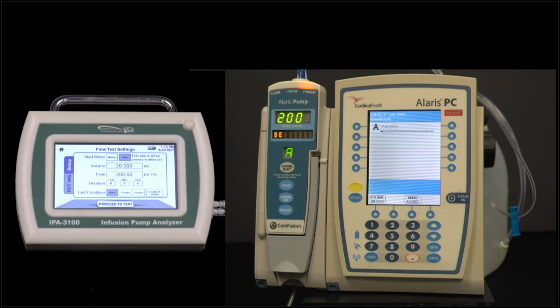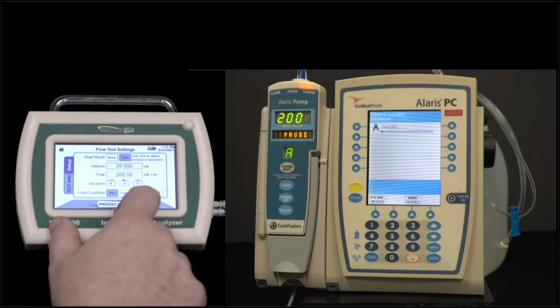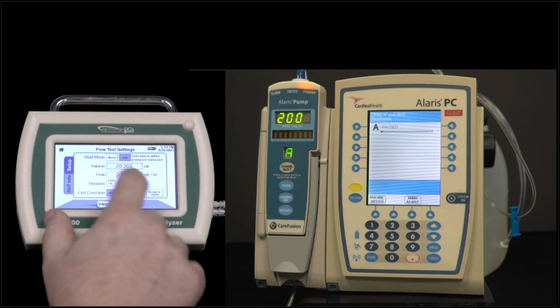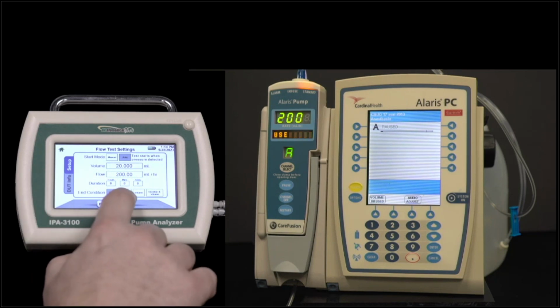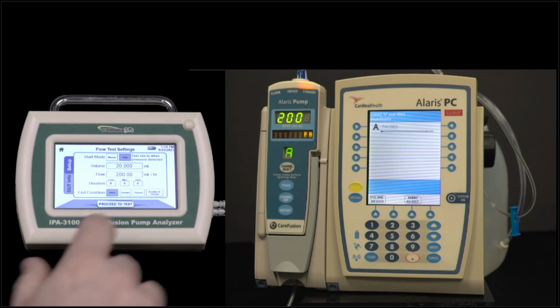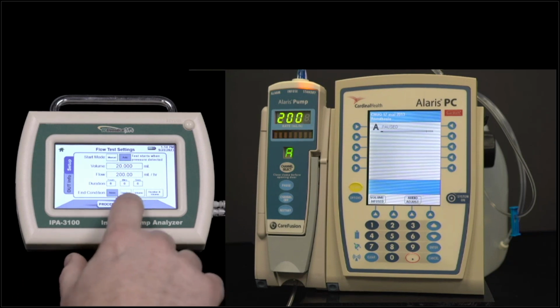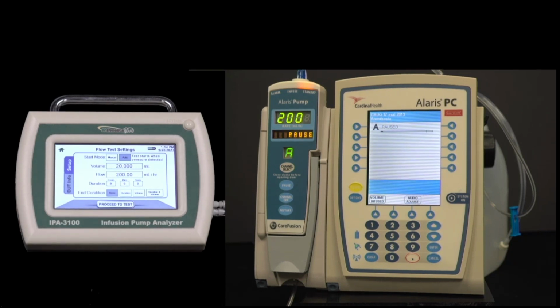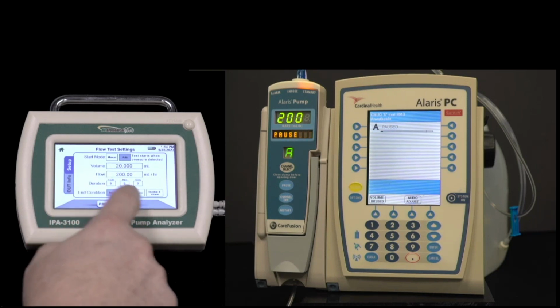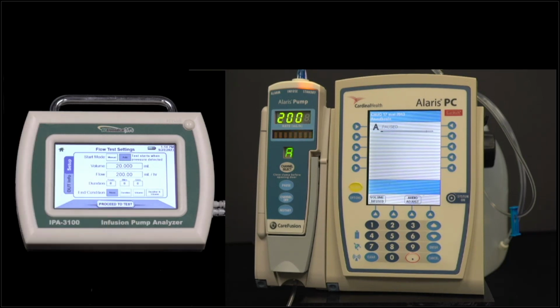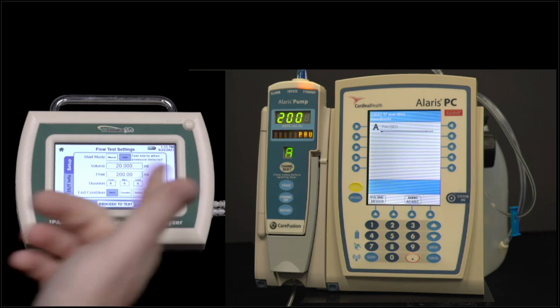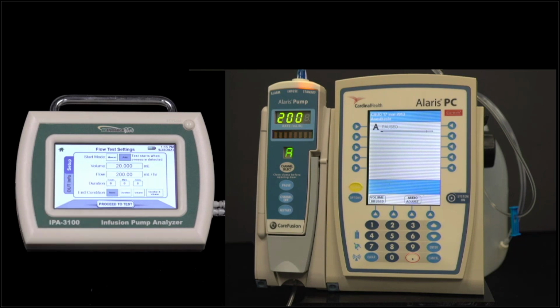When it takes a measurement, it can compare what volume did I measure versus what did you have set, and what flow rate do I measure versus what is set. The duration, again, we can enter that information in if we want the test to automatically stop. So I have the option to stop when I measure 20 milliliters, or I can stop when I hit the volume or the duration. I can stop when I hit exactly 1 hour or whatever, however I have it configured. Or I can have it manually stop by selecting none.